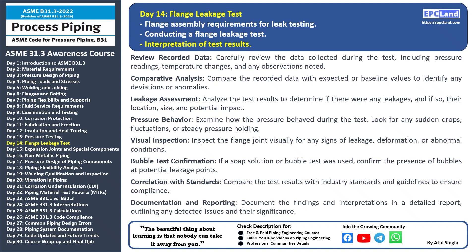Visual inspection: conduct a thorough visual inspection of the flange joint and check for any visible signs of leakage, deformation, or unusual conditions. Bubble test confirmation: if a soap solution or bubble test was employed, confirm the presence of bubbles at potential leakage points. Correlation with standards: compare the test results with industry standards and guidelines to ensure the system's performance aligns with expected parameters. Documentation and reporting: record your findings and interpretations meticulously in a comprehensive report.